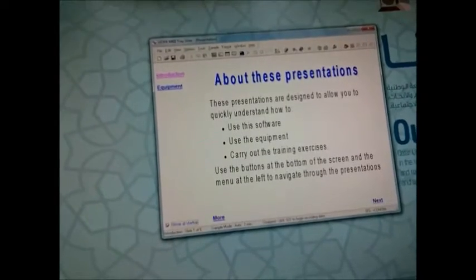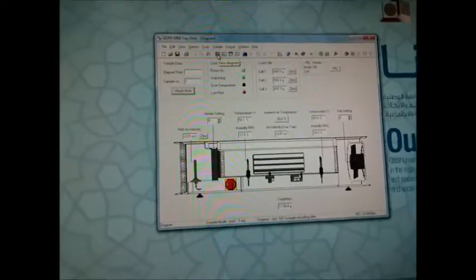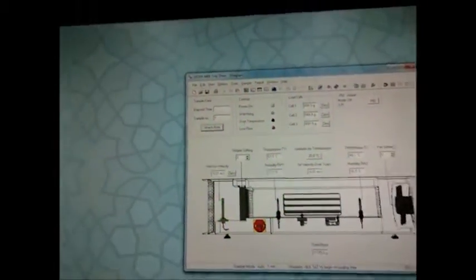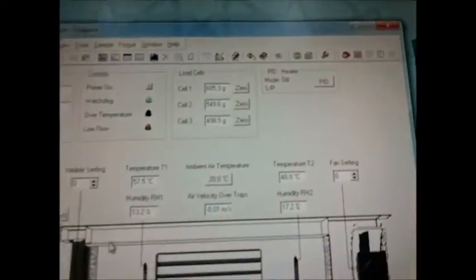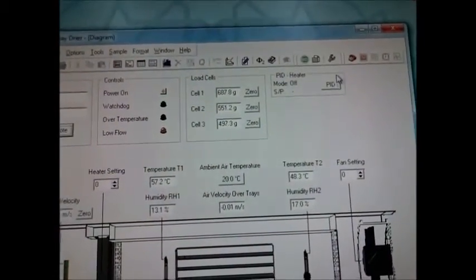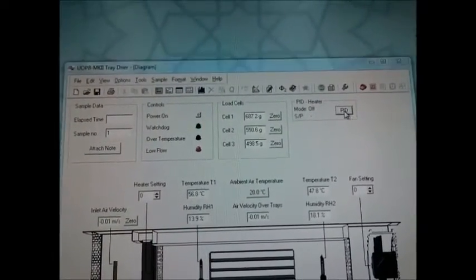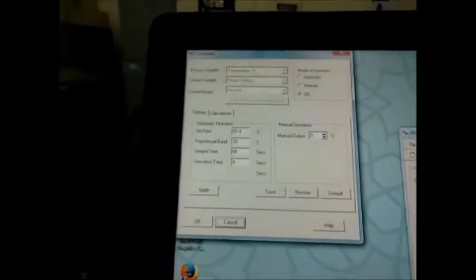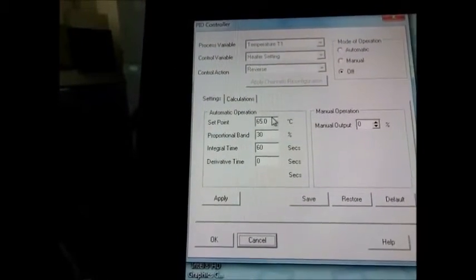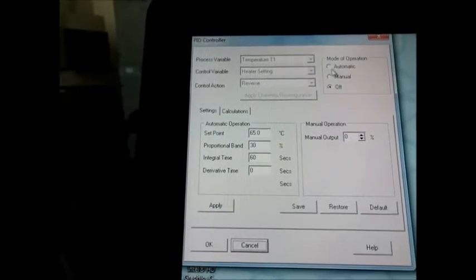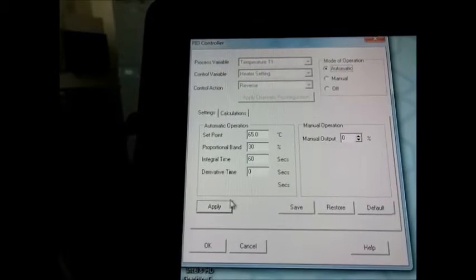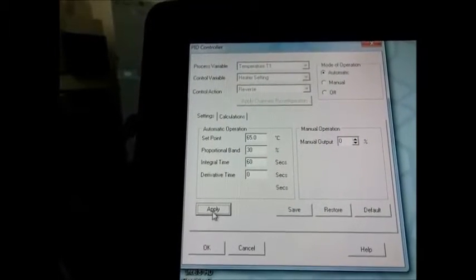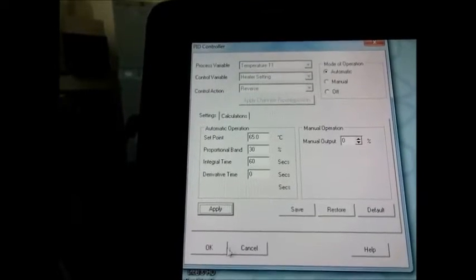Now this is the main screen of the tray dryer software. Then go to mimic diagram by pressing this icon. Now we want to change the heater condition of the tray dryer, so PID, then temperature. You can choose your temperature. So now it's 65 and make the condition automatic. That means it measures automatically and adjusts the heater to be continuously 65 over the trays.